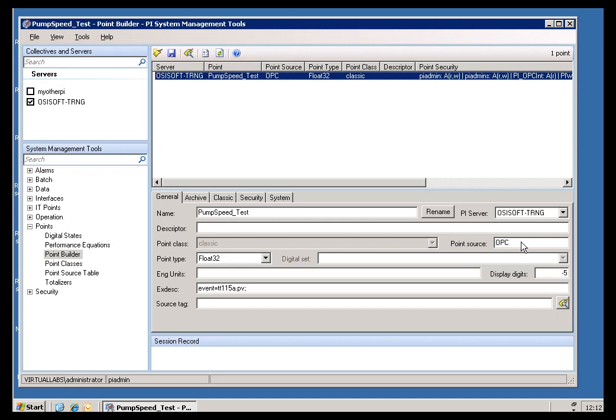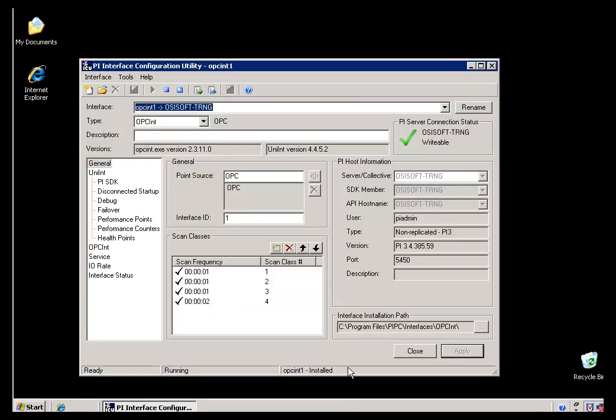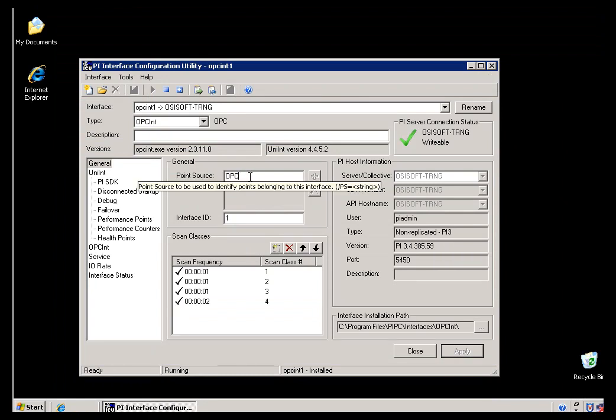Here's a tag that uses the OPC Interface. That means it's being gathered by the OPC Interface. When this OPC Interface starts up, it's looking for all of the tags that have OPC as its Point Source. And when it finds tags, it will go ahead and process them, but it will process them 25 tags at a time.